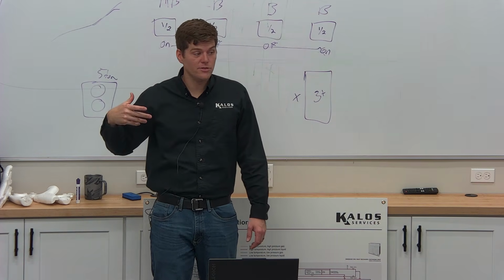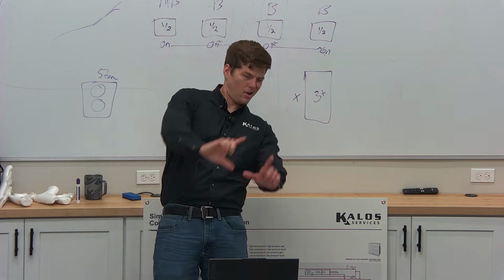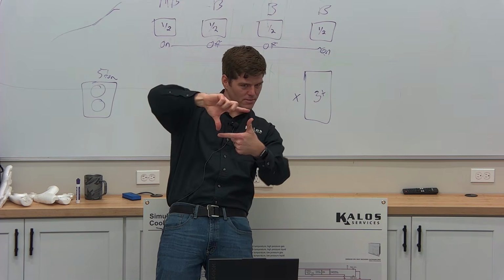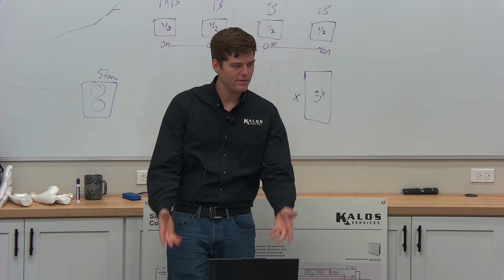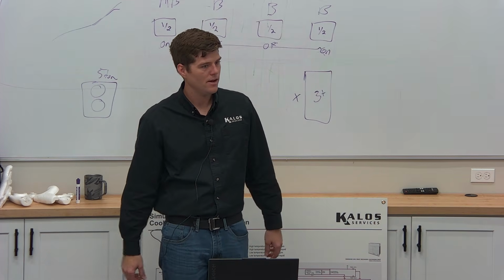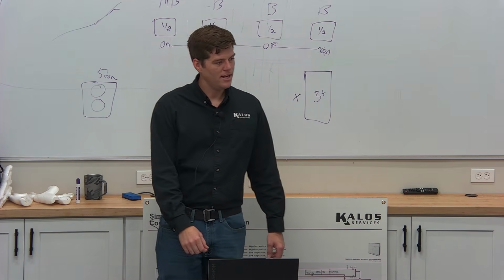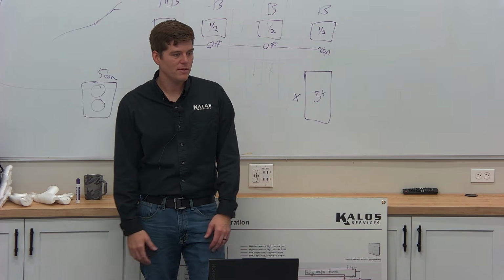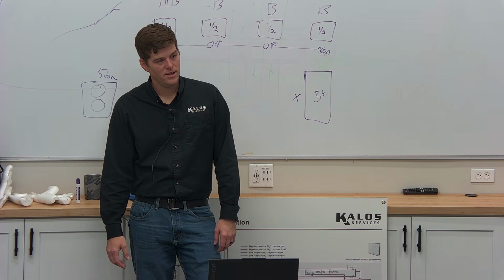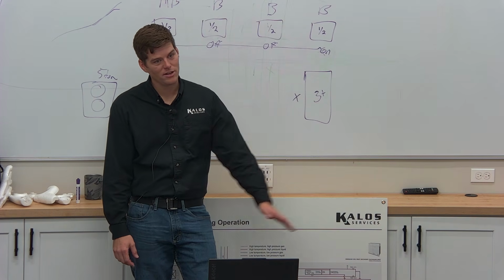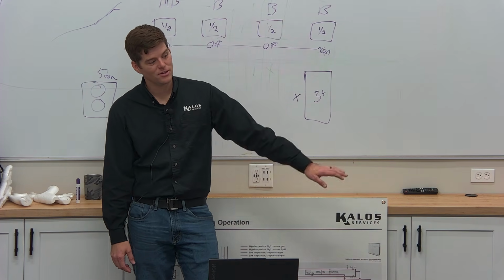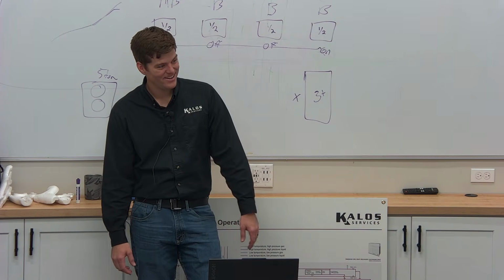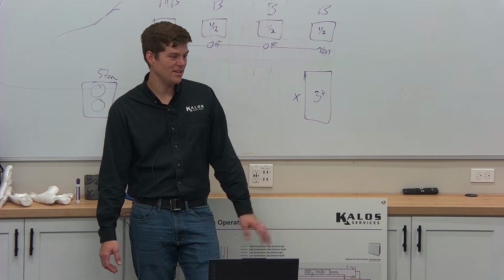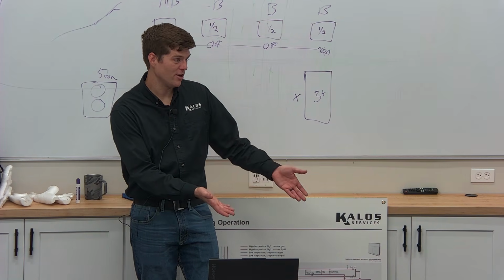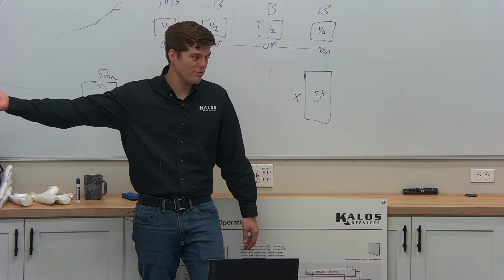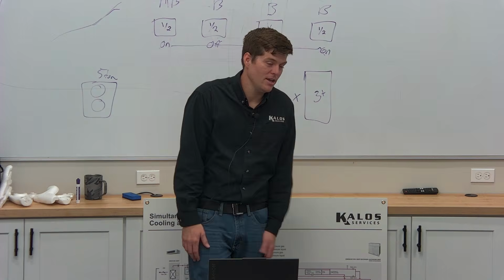Let's say it's 50 feet too short, because I look at it and I go, yeah, that's 5 feet, and it's really 50 feet, you know, and I pencil whip it. And now the system is 15 pounds undercharged. And now the compressor is constantly dipping down in low suction pressure. And now it's on low pressure step down. And it can't meet capacity because it says, I'm hitting my target. I'm sorry that you don't have enough liquid refrigerant. I'm still doing what I'm supposed to do.